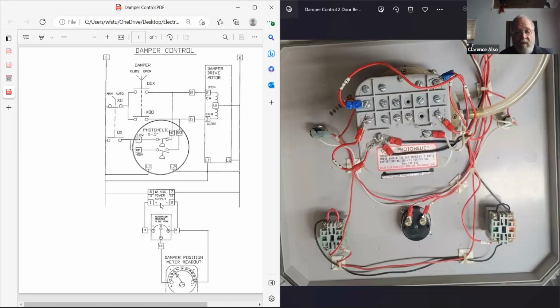If you probe from 2 to 1, you're going to see it say 10 volts. Now I'm going to leave my meter at 2. If I check over here at terminal 4, I would expect 10 volts. And if I check at the wiper here, I would expect, well, I don't know, where's the wiper set? If the wiper is set all the way to the top, it's going to be 10 volts. If it's set all the way to the bottom, it's going to say 0 volts. If it's in the middle, it's going to say 5 volts.